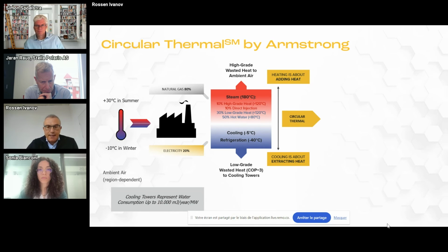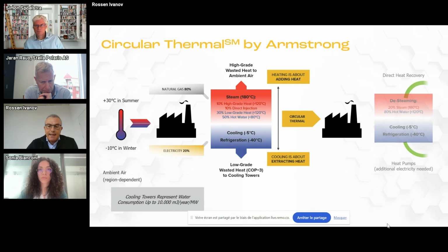On the heating side, as already mentioned, the stacks can be recovered. We're looking at de-steaming, because generating steam with heat pumps is feasible, but it requires quite a lot of capex and opex. So lowering the bar for heat pumps would be to move into superheated water below 120 degrees C. The other advantage is that we can store water relatively easily, while storing steam is quite impossible. There are steam accumulators, but practically they are superheated water tanks, and then steam is flashed.